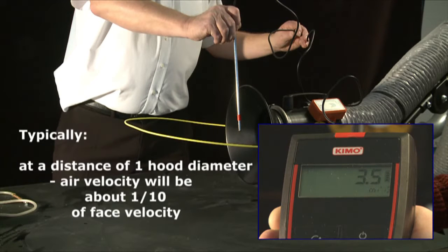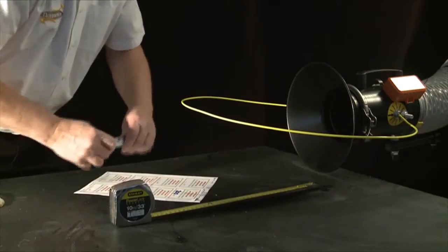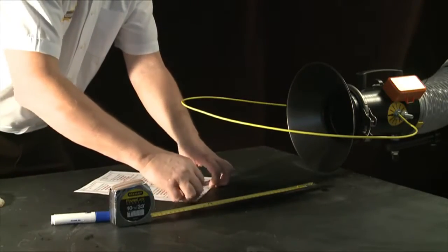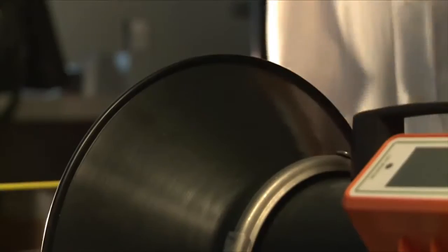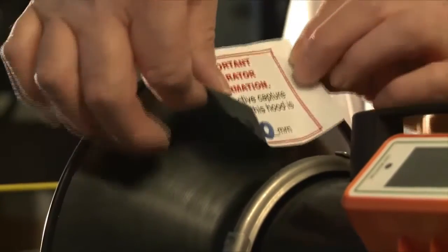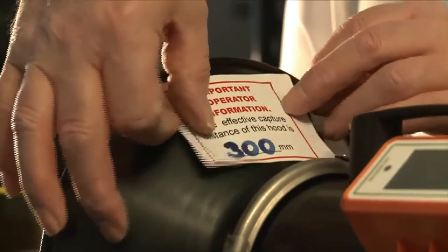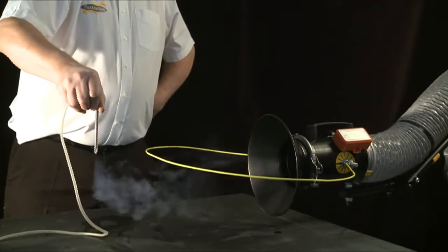Typically, at a distance of 1 hood diameter, the air velocity will be about 1/10 of the velocity at the face of the hood. The capture hood is marked with the effective capture distance for this process. This is almost always smaller than the user expects, and it's due to the fact that the air velocity falls very rapidly as you move away from the face of the capture hood.